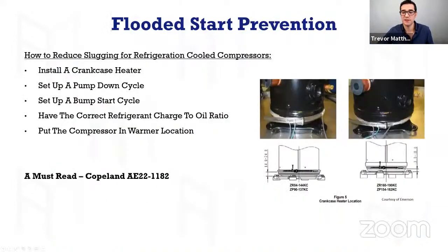So, flooded start prevention. Okay. Install a crankcase heater, and install it properly. If any of you caught it on the very first slide when I was talking about low oil, you saw two of these crankcase heaters on there, and one was above the sight glass, so bad. You need to put the crankcase heater where the compressor manufacturer tells you, because if you put it too high, it's going to overheat that compressor and cause a failure. It needs to go in a specific place. So here's a seam. You need to make sure you put this on here properly and you torque it right, because the crankcase heaters are going to fail prematurely if you don't install them right.